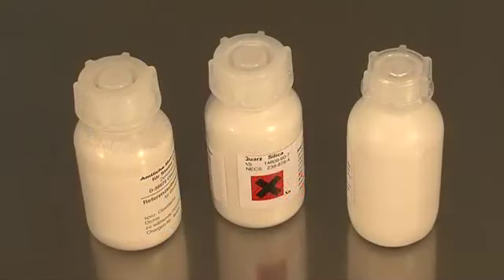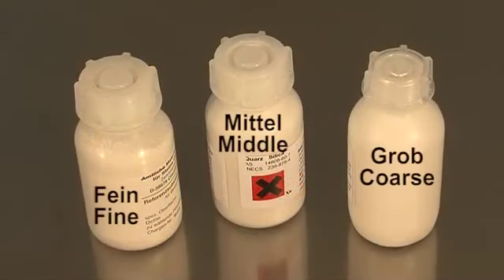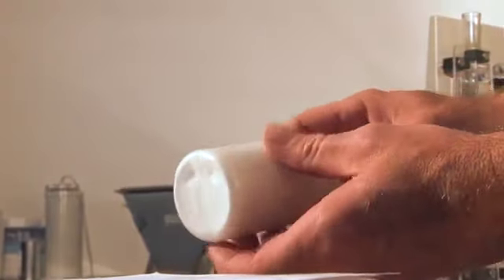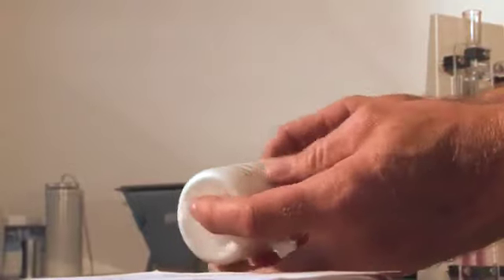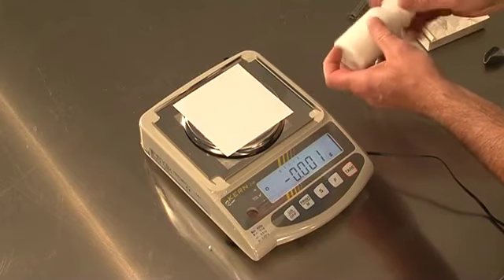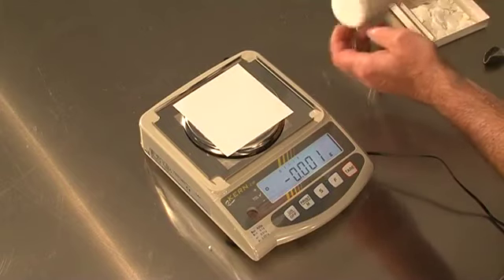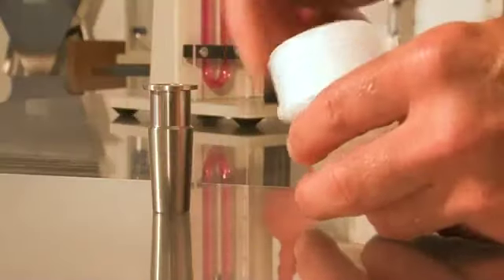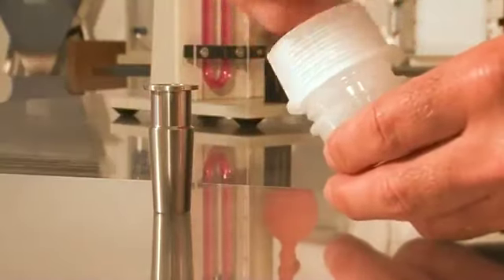The appropriate apparatus constant K must be determined separately for each reference substance. The reference substance for determining the apparatus constant is shaken for at least 2 minutes in a closed bottle in order to dissolve any agglomerates. The bottle is then left to stand for 2 minutes. Finally, the powder bed is stirred with a clean, dry rod in order to evenly distribute the fine particles.